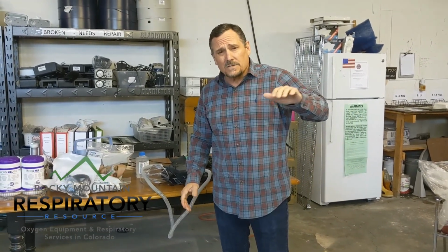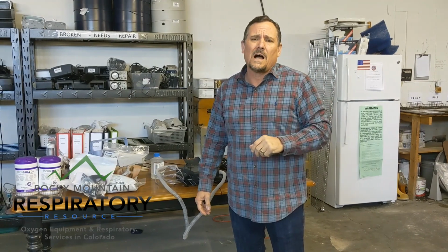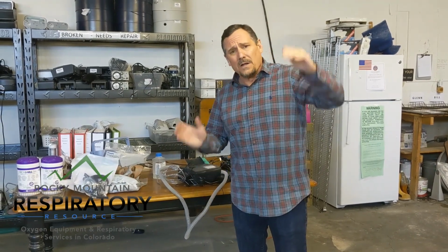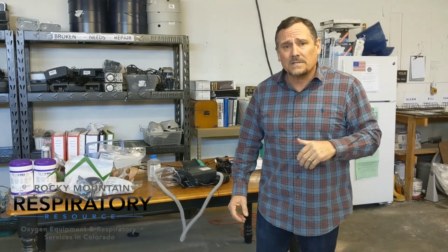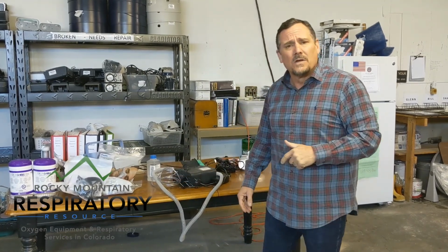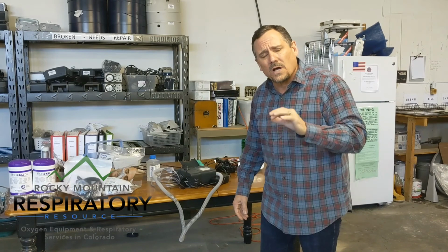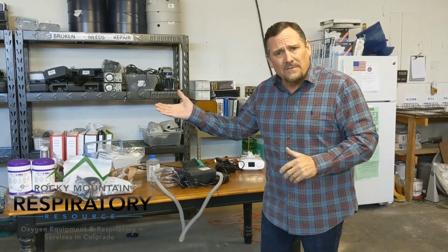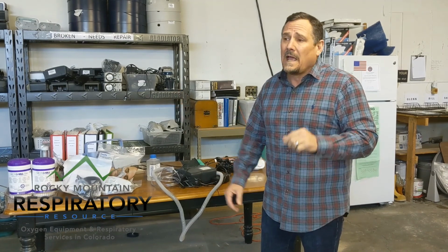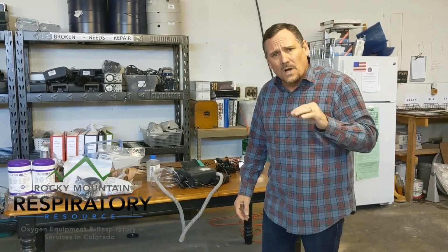Now, as far as settings, we do sleep studies. We can ramp BiPAP all the way to 30 centimeters of water, and usually we don't go any lower than 5 centimeters on the EPAP. But a patient, depending on how much fluid they're holding, how obese they are, how much activity they have, how big their neck and their epiglottis are, these changes have to be done with a sleep study to make sure that the pressures that we are setting are enough to keep the oxygen level up above 88% all night long. And usually with 1 or 2 sleep studies, we're able to get that.